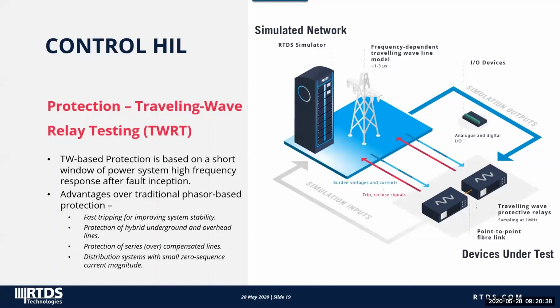Traveling wave-based protection schemes investigate the current and voltage waves that are generated by a fault. Commercially available traveling wave relays normally have a sampling frequency in the range of 1 megahertz. To evaluate and verify the performance of traveling wave relays, a testing platform that can provide traveling wave phenomena with sufficient accuracy and time resolution in a closed loop scenario is highly desired.